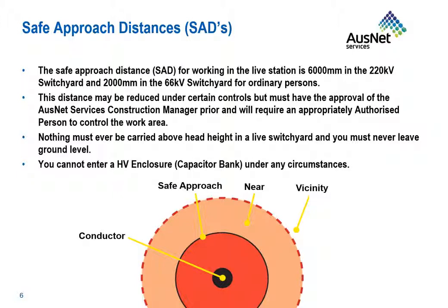The safe approach distance for working in a live terminal station is 6 metres in the 220 kV switchyard and 2 metres in the 66 kV switchyard for ordinary persons. This distance may be reduced under certain controls but must have the approval of the AusNet Services construction manager and will require an appropriate authorised person to control the work area. Nothing must ever be carried above head height in a live switchyard and you must never leave the ground level. You cannot enter a HV enclosure, for example a capacitor bank, under any circumstances.